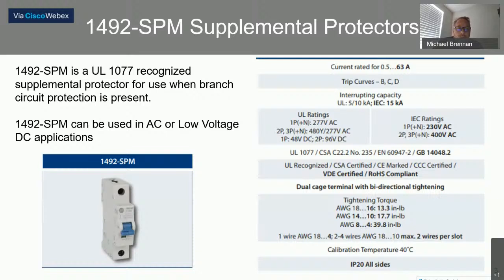That is the 1492 SPM. It is a UL 1077 recognized supplemental protector. It's used when a branch circuit protection device is already present. The key point is that it can be utilized in AC or low voltage DC applications. So we're talking today specifically about 24 volt circuit protection. That is a small portion of the use of miniature circuit breakers in this case, but we see this often in applications being utilized.